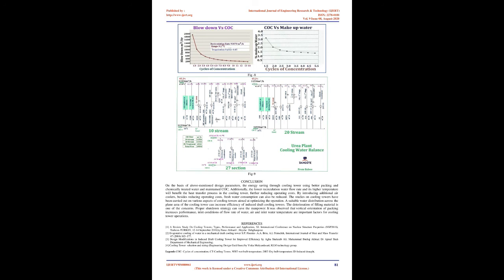Conclusion. On the basis of the above-mentioned design parameters, energy saving is possible through the cooling tower using better packing, chemically treated water and maintained cycles of concentration. Additionally, the lower recirculation water flow rate and its higher temperature will benefit the heat transfer process in the cooling tower, further reducing operating costs. By introducing additional air coolers, besides reducing operating costs, fresh water consumption can also be reduced.